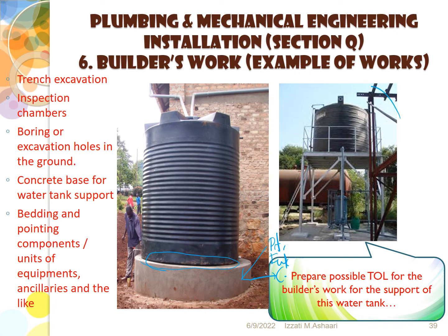Then let's say if you are referring to this particular design, this is the cold water system but outside the building. So what are the builder's work? First, you have to measure for pit excavation. Why? Because you can see there are footings over there. After pit excavation, then there is formwork, and then after that the concrete work. Then you have to install this steel structure. All of that are considered as the builder's work because you need to have this in order to put in the water storage tank.